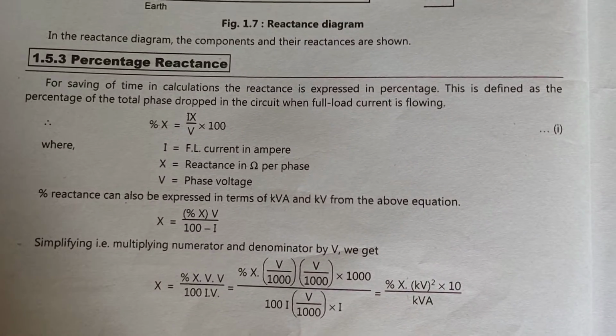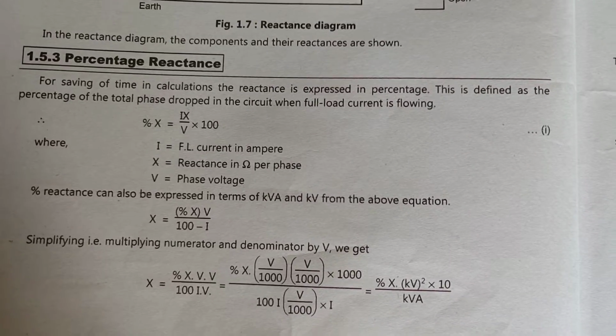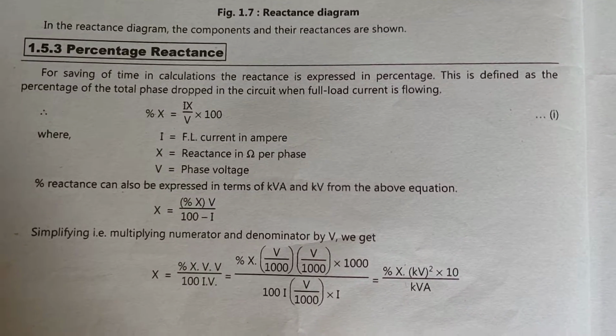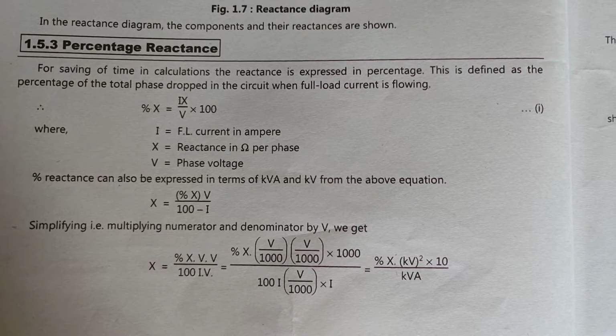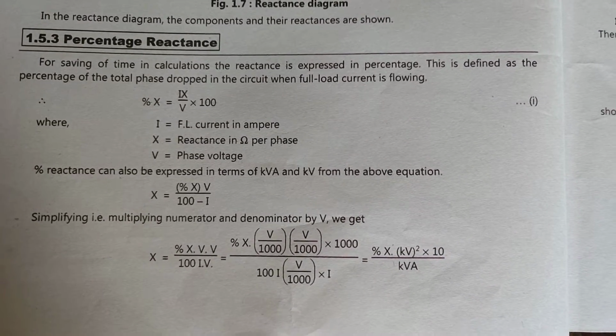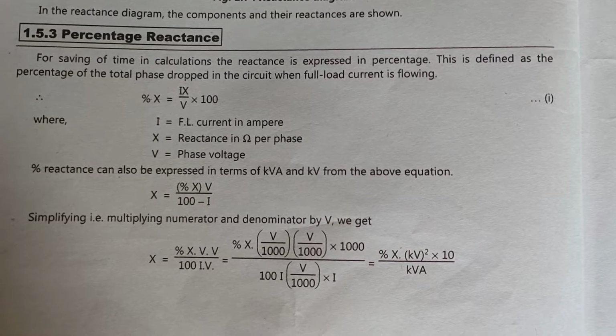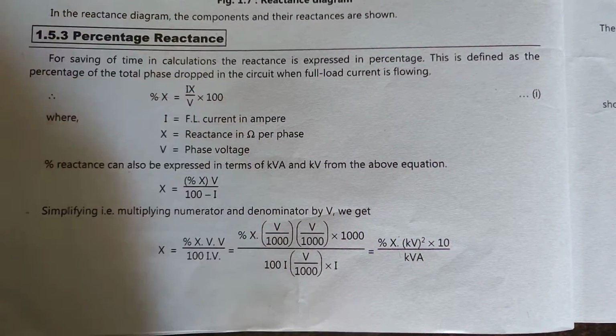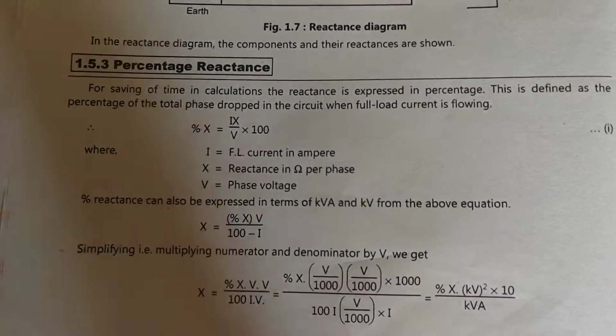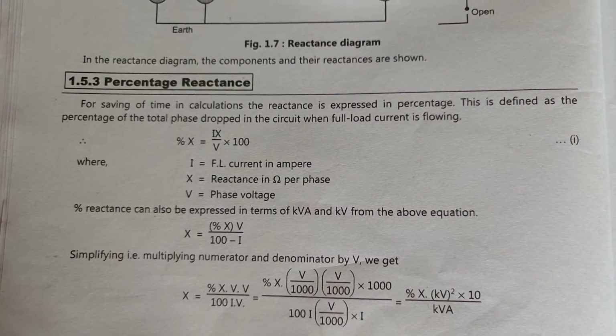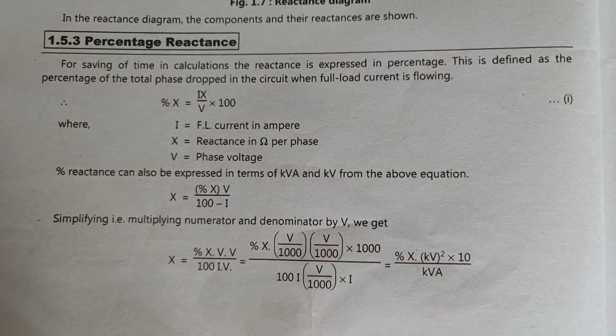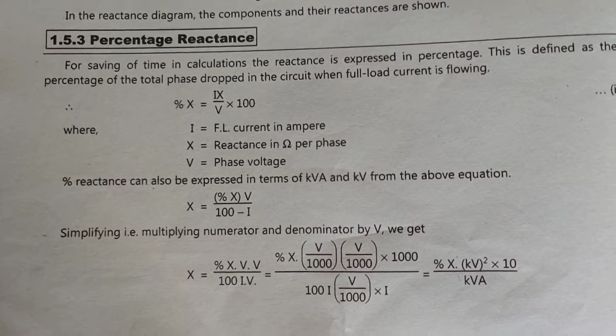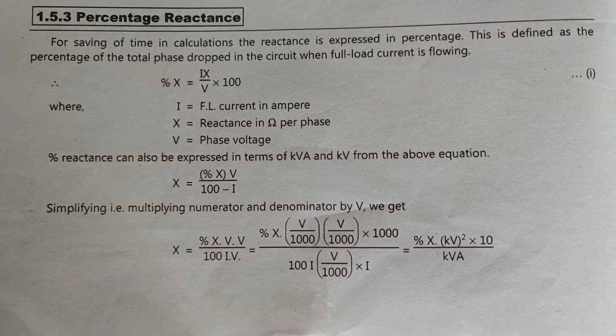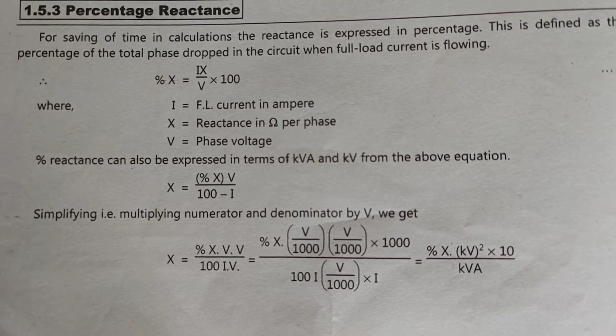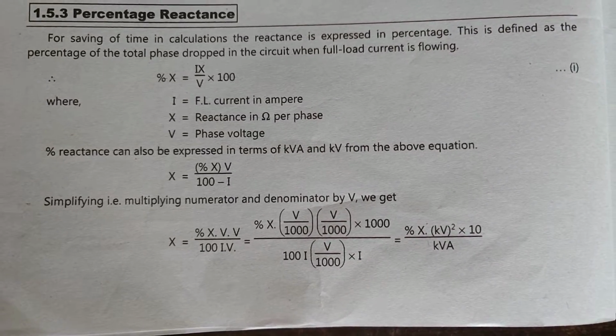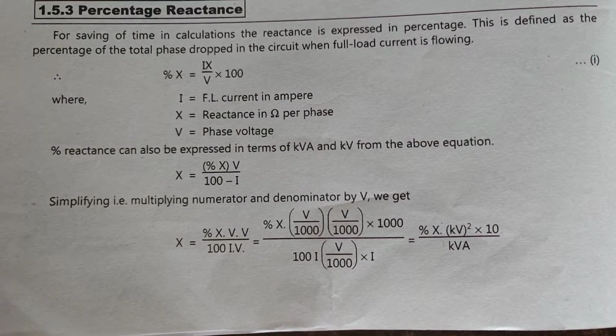For saving of time in calculations, the reactance is expressed in percentage. This is defined as the percentage of the total phase voltage dropped in the circuit when full load current is flowing. Therefore, percent X equals IX upon V into 100, where I is FL current in ampere, X is reactance in ohm per phase, and V is phase voltage.